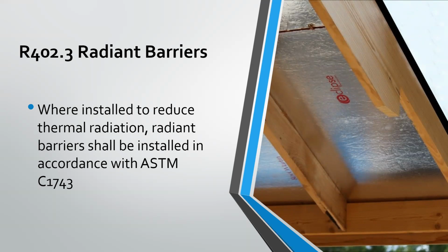However, now looking at it from the standpoint of an ASTM standard, they're looking at it from a practical standpoint of fire hazards, mold and moisture, and deterioration of wiring components, due to the fact that you've got moisture buildup because you have a very hot surface against a cold surface. Even when it's sunny but cold outside, that radiant heat is still making it somewhat into the attic. It can heat up a radiant barrier surface, and any cold surface against it is subject to condensation. So it needs to have proper installation done. There's now a standard that needs to be followed for that. I'm glad to see that it made it into the code.